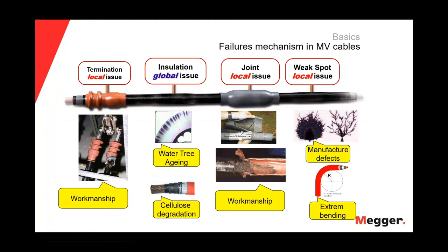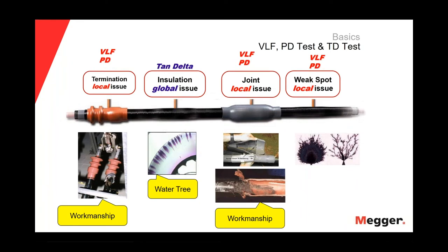And depending on what kind of problems we are dealing with, we can use VLF or partial discharge to detect local issues, okay? In the case of the VLF, to convert a local issue into a fault, that problem should be severe or a big problem. But if the local issue we are looking for is a small one, we will not convert it into a fault with the VLF, and then maybe we should use partial discharge. If we are dealing with global issues, for instance, water trees in the XLPE insulation, then we will use the tan delta test, okay? That is what we will discuss in detail in the next slides.